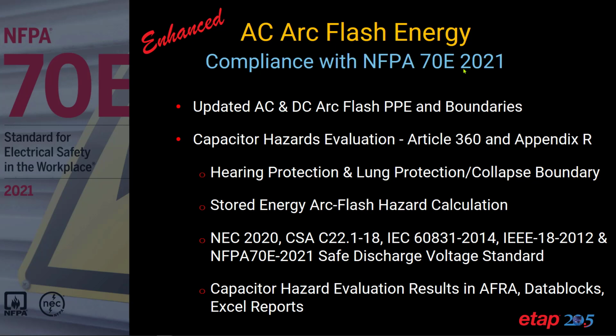NFPA 70E 2021 has provided valuable information for electrical workers on how to establish a safe capacitor discharge voltage and has provided guidelines for the risk assessment of capacitors to assess arc flash hazards. This latest revision now includes guidance for labeling capacitors in facilities, recommending labels for capacitors operating at or greater than 100 volts with stored energy greater than or equal to 10 joules.